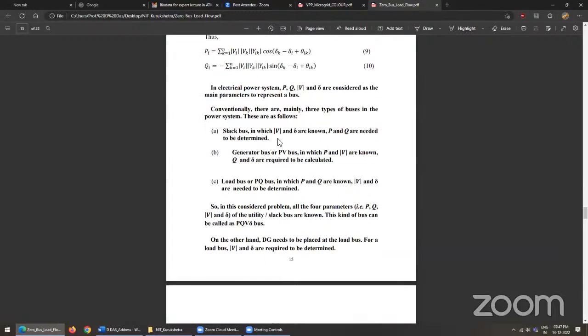So one is the slack bus — it is known that voltage and angles are known, P and Q need to be determined. Another is the PV bus, where P and voltage magnitude are known, Q and delta are required to be calculated. Load bus or PQ bus, in which P and Q are known, voltage and delta need to be determined.